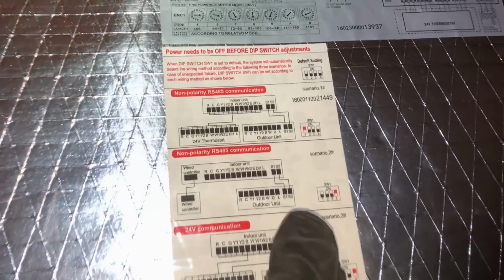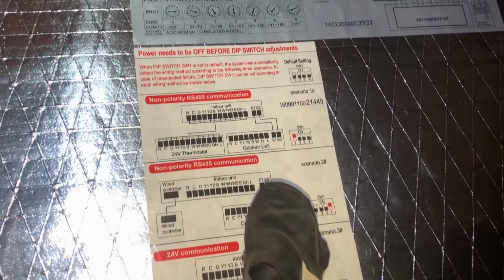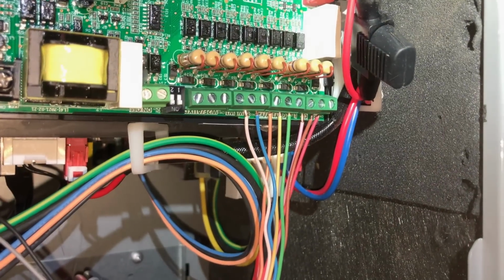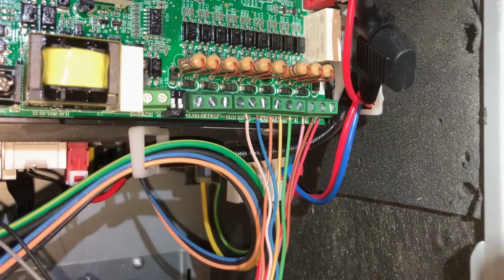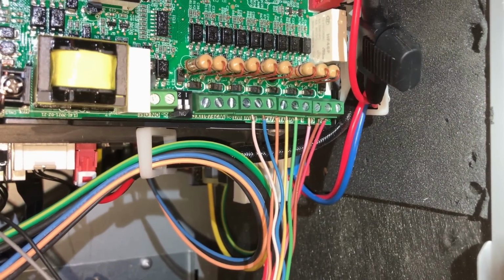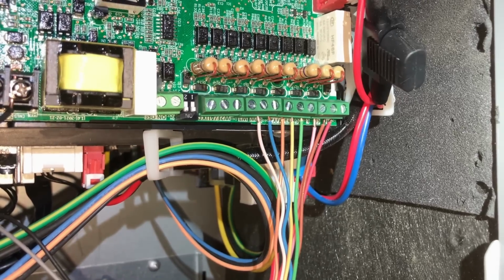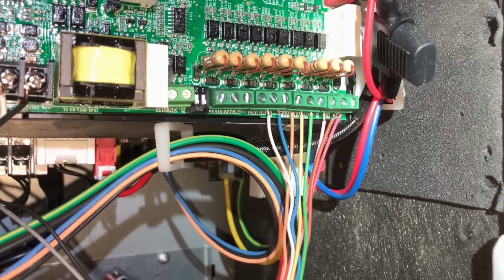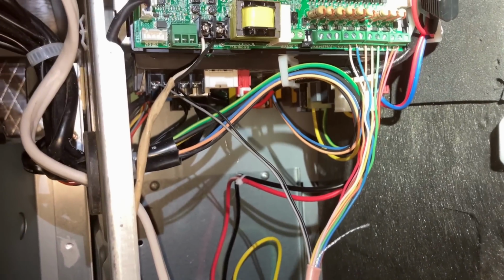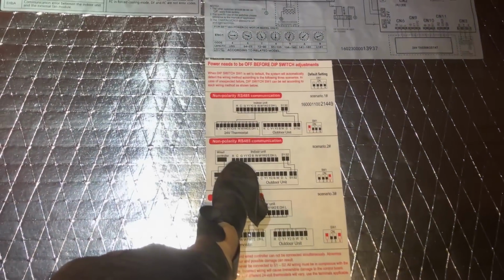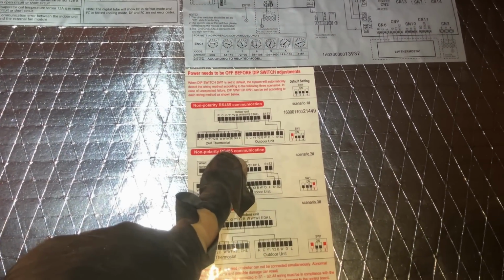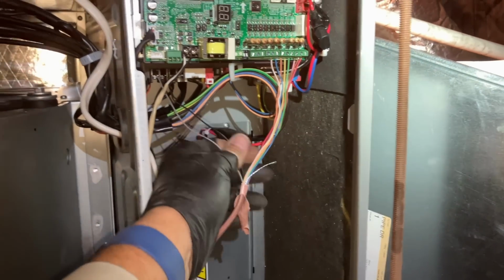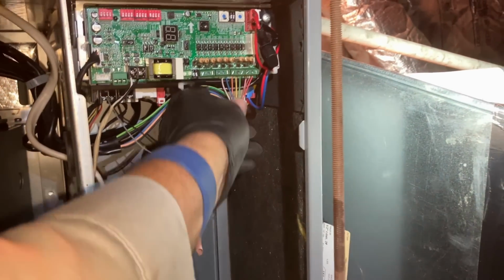Our outdoor unit, we're wiring with S1, S2 to S1, S2. We had, and we still do have 8 conductors wired from RC to L to B to Y1, Y2, W1, G for fan. We have all that wired in, and then we have 2 other conductors remaining, and then we saw this on the inside front cover of the air handler, non-polarity RS485 communication. So our gray and our black wire is going to be our communicating wires. We're going to leave this attached for now.